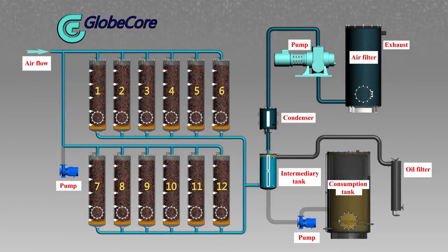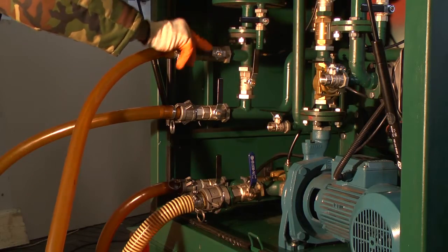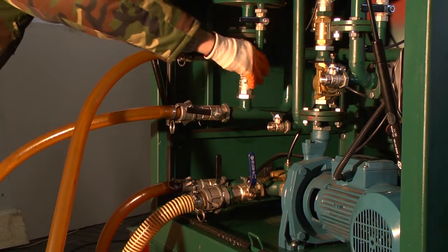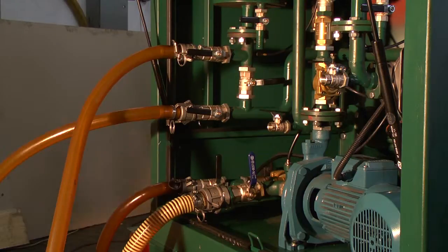Regeneration machines can be operated continuously. The only difference with a regular machine is an additional bank of sorbent columns. During operation, part of the columns regenerate oil, while the rest are in sorbent reactivation mode. After reactivation is complete, the machine is ready for operation again. The bypass line opens, the regeneration system and the degasser continue to treat the oil in tandem.